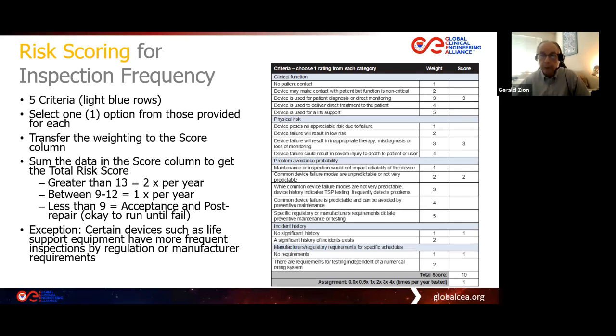We want to double check it based on how this medical device is maintained, how it's used, and sometimes abused by the clinical staff at our location. They may be two different things, and you may need a more frequent inspection interval than the medical device manufacturer is typically using or recommending.